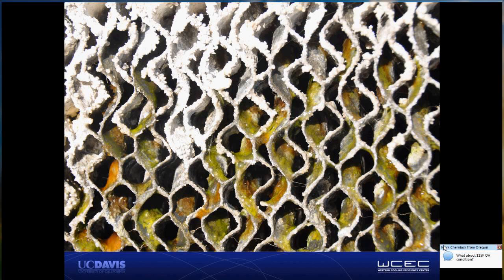And the reason that there's so much scale and, in fact, algae growth on the system is because the system was not being controlled properly by the customer. Not that it wasn't being maintained, because this could be washed and everything seasonally. It's because it wasn't being controlled properly. The set point for the dual cool system was too low, so it was never turning off during the middle of the night. It was running even when it was only 50 degrees outside. The media was never allowed to dry, and when the media was never allowed to dry, it provided this perfect basis for growth and solid deposits.